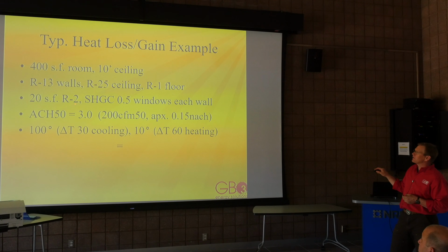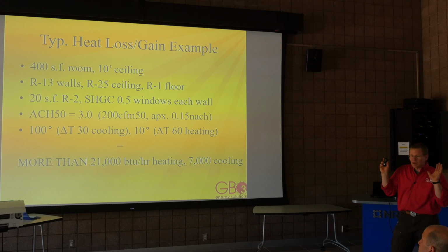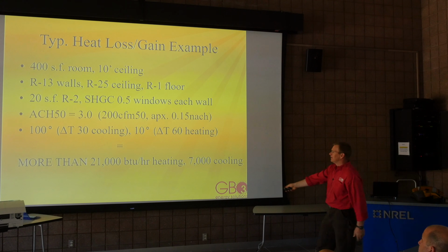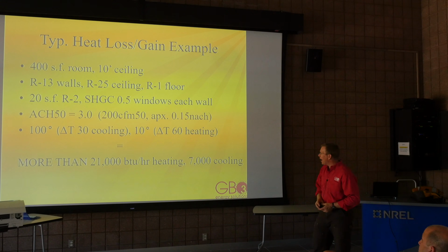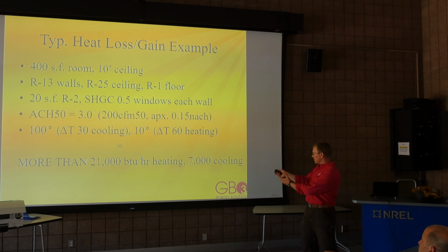We have 20 square feet of R2 glass with a solar heat gain coefficient of .5. Air changes per hour is 3, so that's about 0.15 natural air changes. Again, you don't need to know all this. Say it's 100 degrees outside, so our delta T is 30 for cooling, and it's 10 degrees in the winter, so to get to 70 degrees our delta T is 60. So that room on a cold day is going to take 21,000 BTUs per hour to heat it, and 7,000 BTUs for cooling. And this is very true in Colorado.